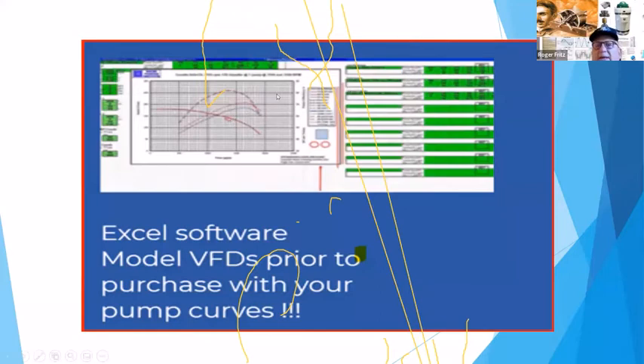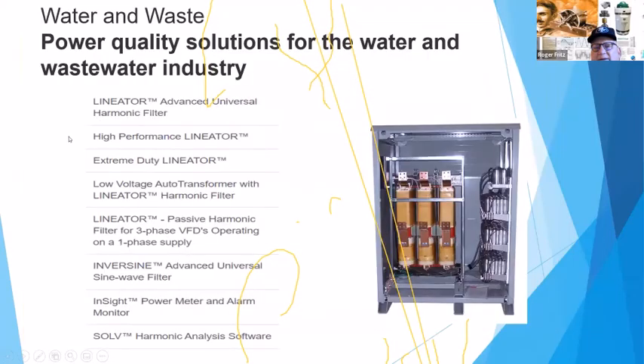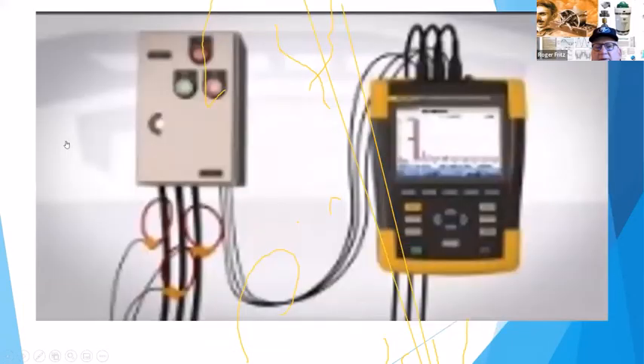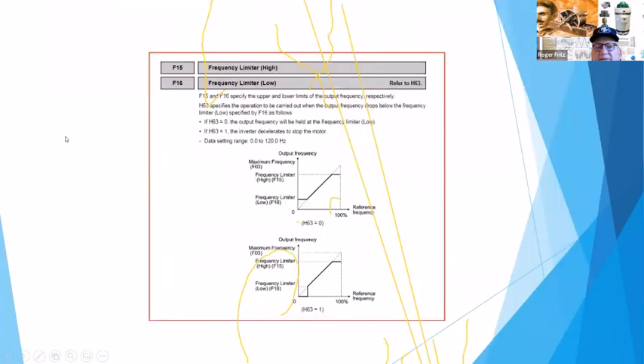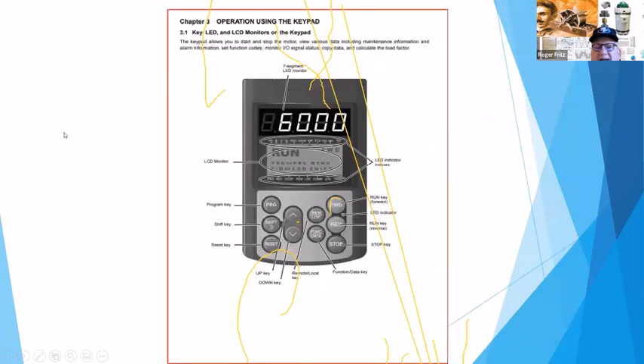Because as you slow a pump down, yes, the horsepower drops by the affinity law, but the GPM also drops. So you've got to look at total acre feet to get to a crop application to maintain that. So a lot of times you may just be running longer, and your total kilowatt hours, even though you have a VFD on, that you were expecting a 30% cube loss savings, end up being negligible, because you also have losses in the drive itself, these transistors and components inside here.